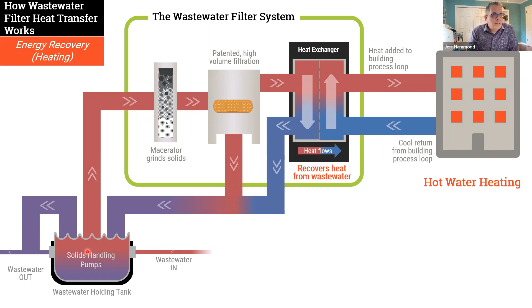Yep, absolutely. It would pair similarly, though this would be a much larger loop where a geofield feeds the majority of its energy into the district. Depending on what's happening, you could have a dedicated energy plant outputting high temp hot water into the field, with heat exchangers in each building to draw energy from the loop for domestic hot water or heating. Or with a low temp ambient loop, the same principle applies, but each building would have heat pumps, chillers, or hot water heat pumps to take energy for those uses.